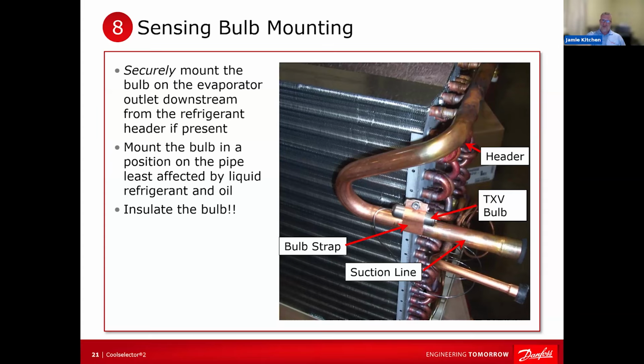So when you put your coffee cup on your dashboard and you do the old movie scene of going around the corner fast, right? Your coffee cup goes towards the outside of the turn. Laws of physics. Your oil is going to do the same thing on a bend. So if you look at that bend there, it's going to shoot to the outside after the header. It's going to shoot to the outside of that bend, and then it's going to shoot to the outside of the bend down at the bottom of that suction line, leaving the evaporator. So put the sensing bulb opposite of that.